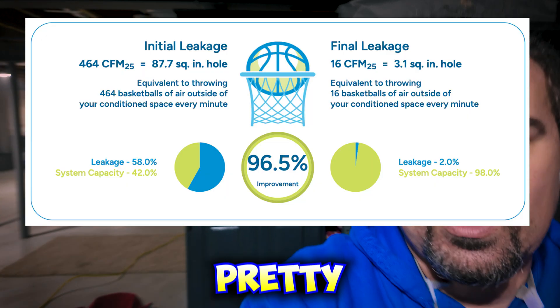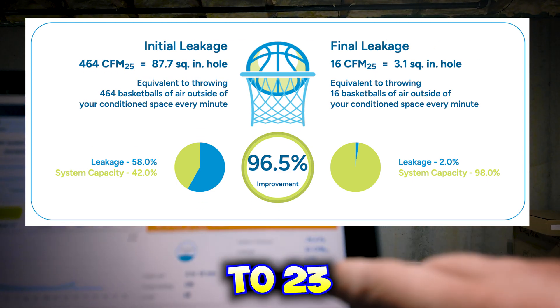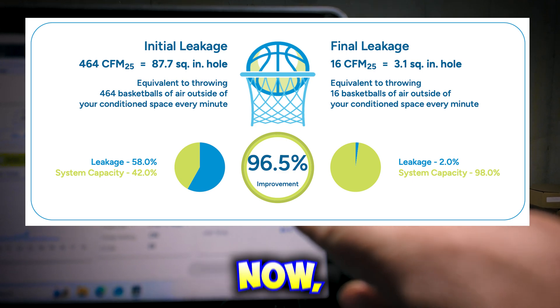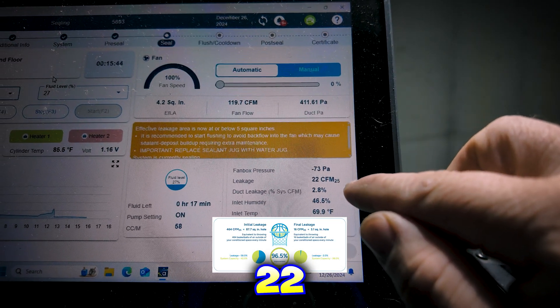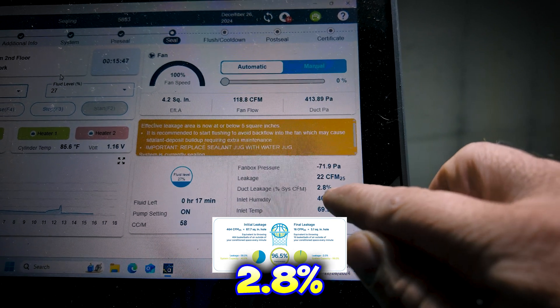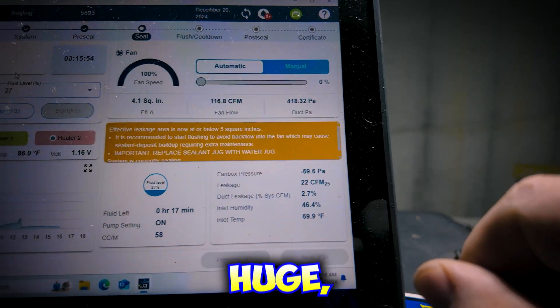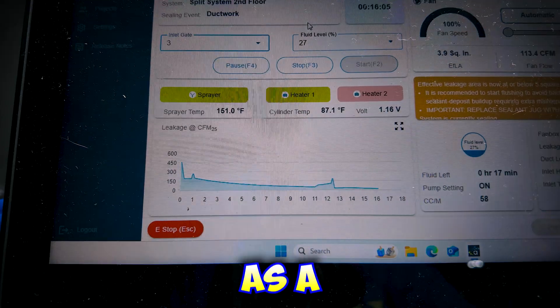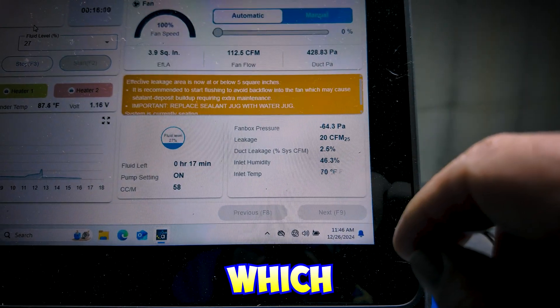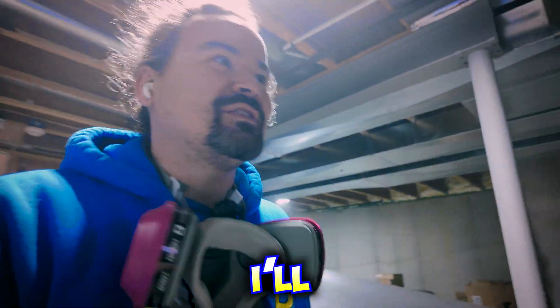All right, this is pretty much the stopping point for system one. I've sealed it down to 22 basketballs of air — 2.8% duct leakage. And you can see the real-time graph there. It actually got down to 21 CFM, which is 2.5% duct leakage. This is a huge increase in performance.